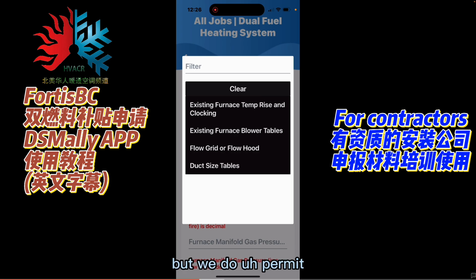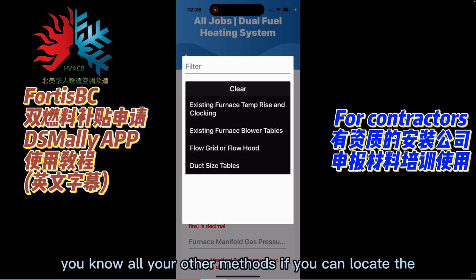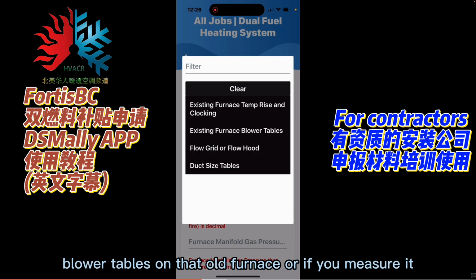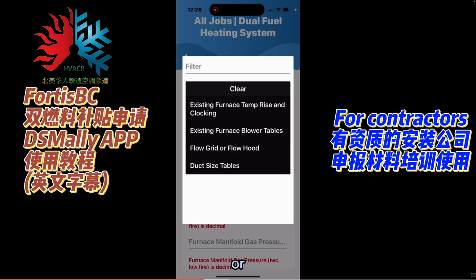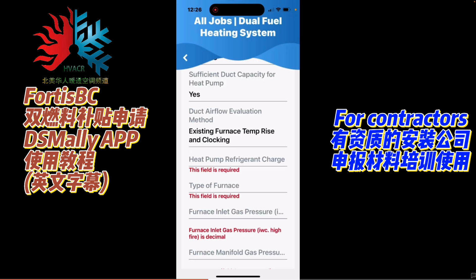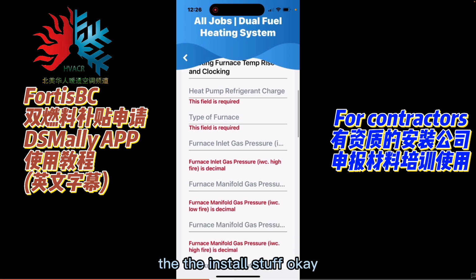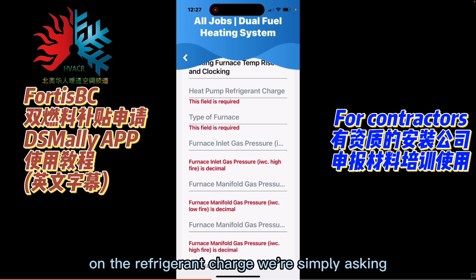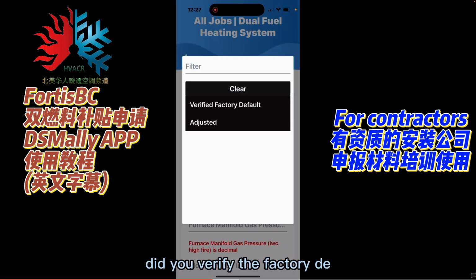But we do permit all your other methods: if you can locate the blower tables on that old furnace, or if you measure it through a flow grid or flow hood, or perhaps through the duct size tables offered through CEE and NCI, and other methods, okay? Now we get into the install stuff, okay? With the heat pump itself on the refrigerant charge, we're simply asking, did you verify the factory default or did you adjust the charge?